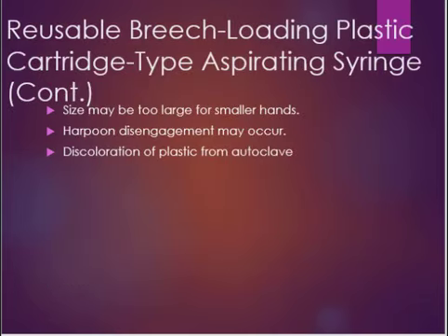Now the disadvantages, again, the size may be too large for smaller hands. The harpoon in this one can disengage, and there can be some discoloration that happens on the plastic from the autoclave.